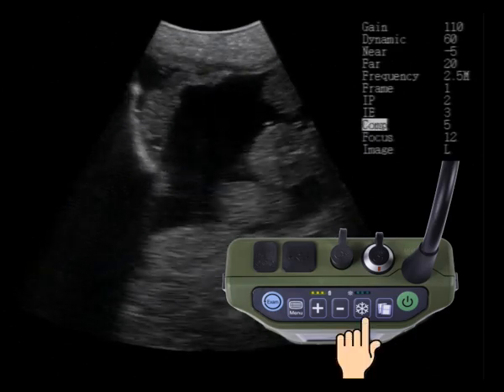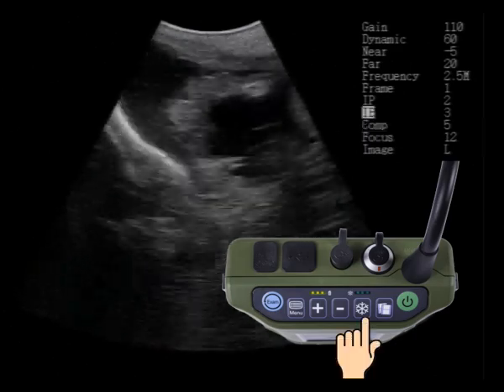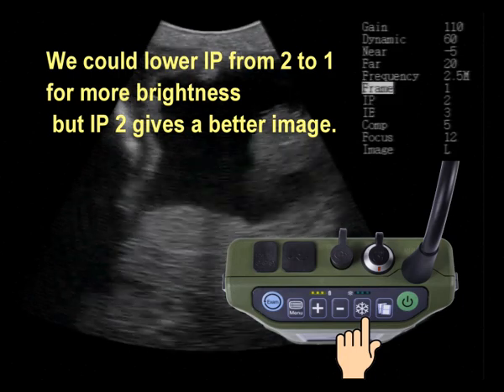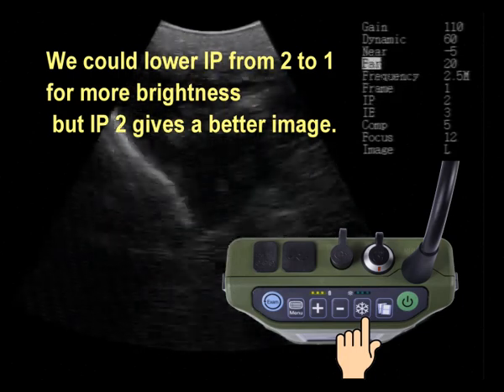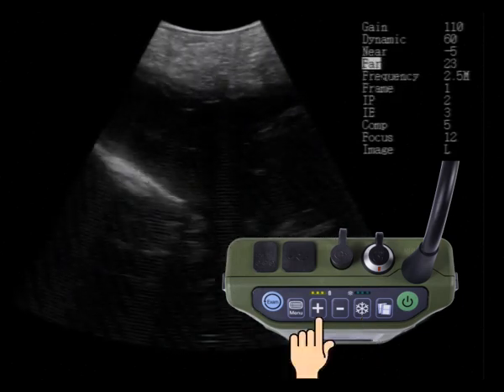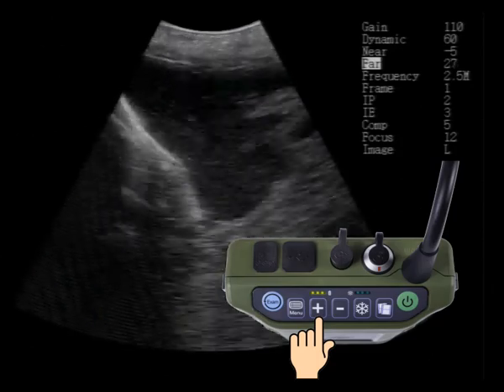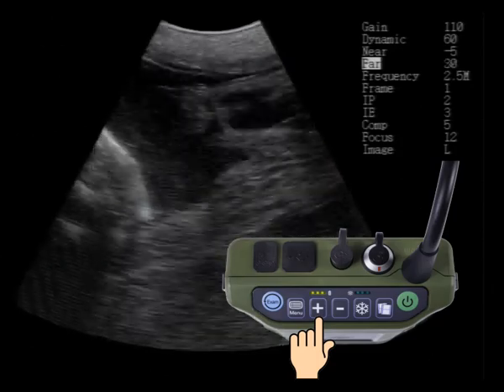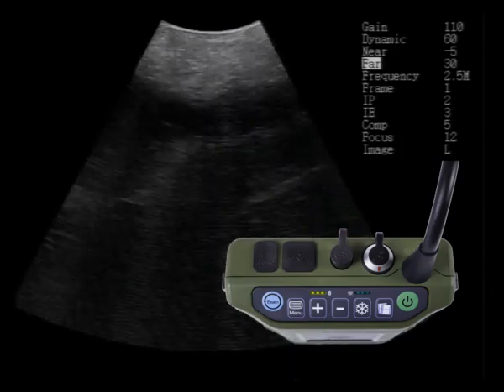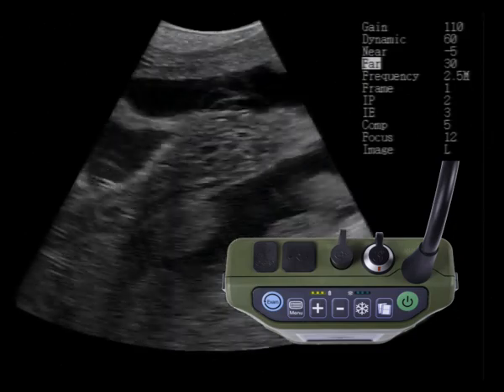We press the freeze button to scroll back up. IP settings can change brightness considerably, but IP2 gives a better image so we'll leave it there. We scroll back up and we're going to increase the far gain to 30. Our image is getting brighter behind us.